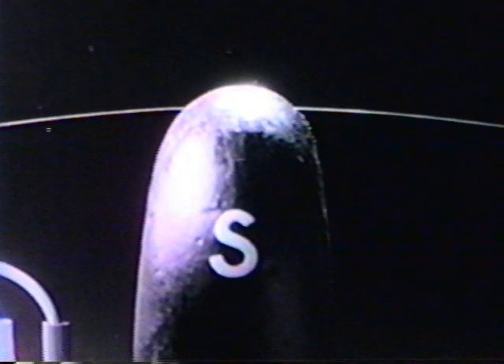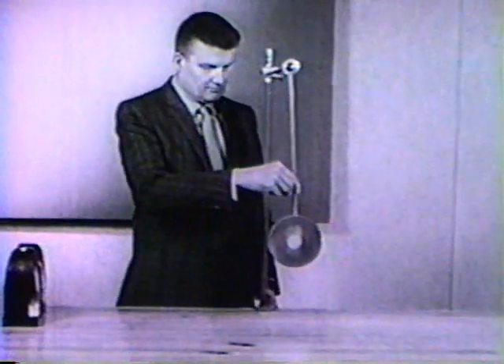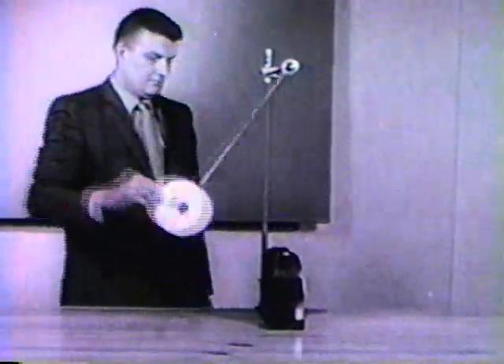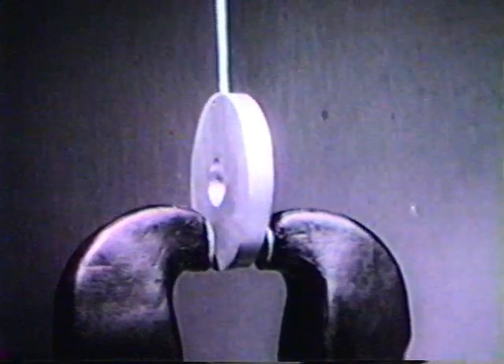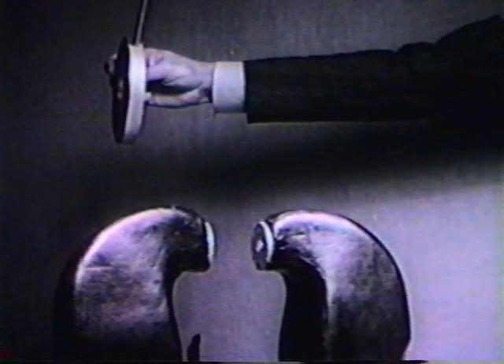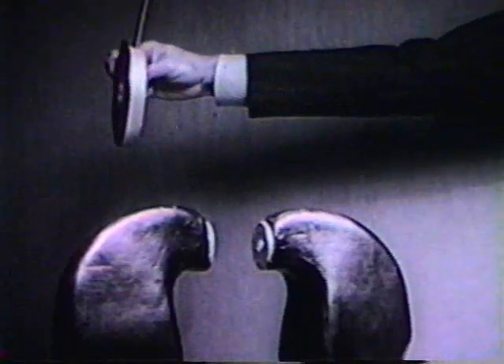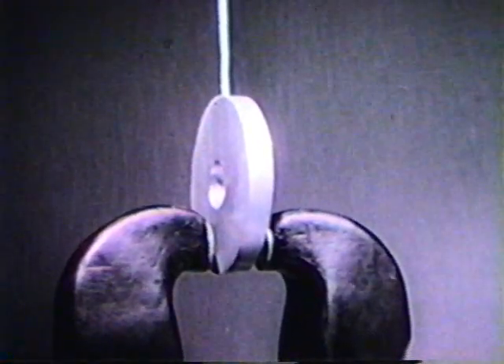Recall this response when the current was abruptly changed. In an instrument, this vibration is reduced by damping the coil mechanism. Eddy currents are produced in this aluminum disk by induced voltage. These currents are proportional to the velocity of the disc through the magnetic field and react with the field to oppose the motion, which is thus damped. PMMC mechanisms are damped by winding the coil on a lightweight aluminum frame. As the frame moves through the magnetic field, motion is damped by the eddy currents produced in the frame.